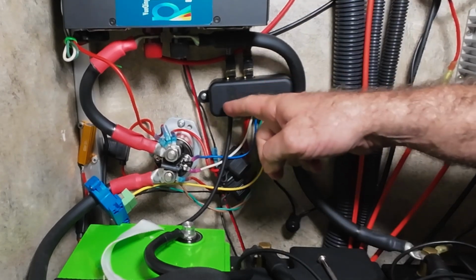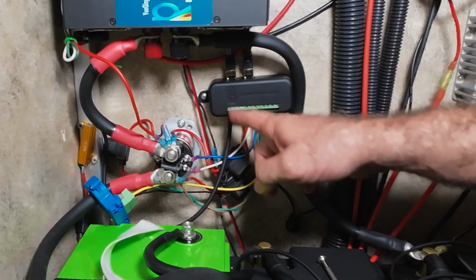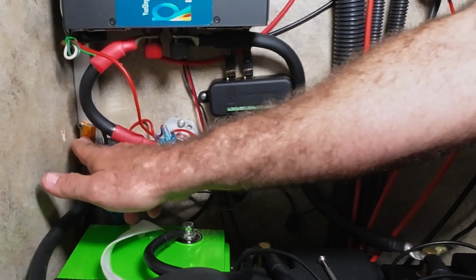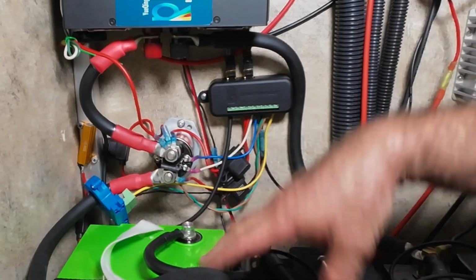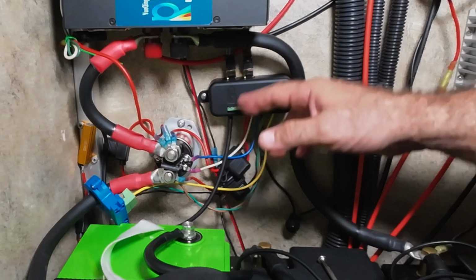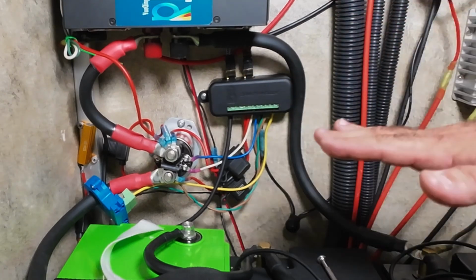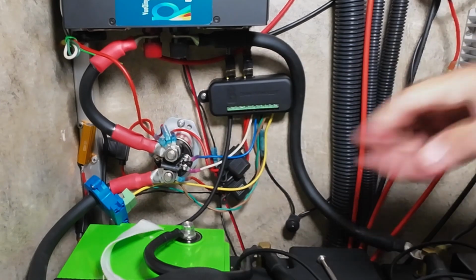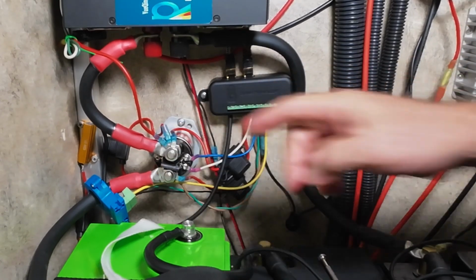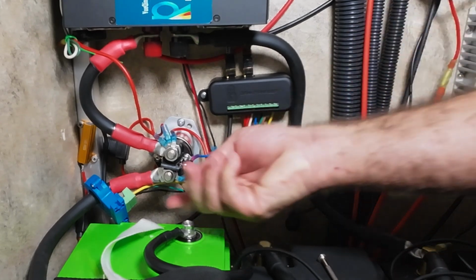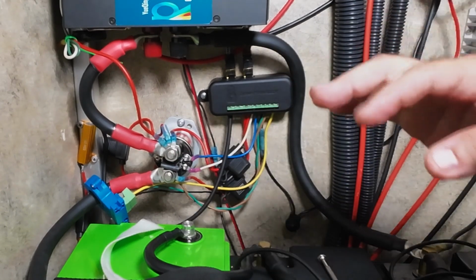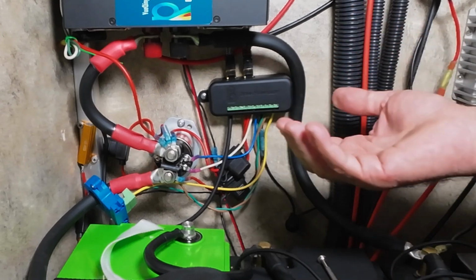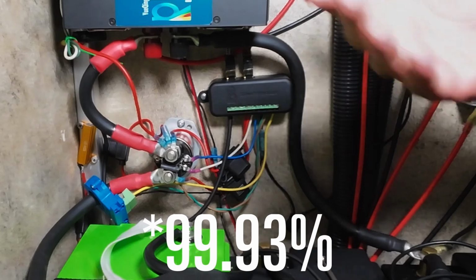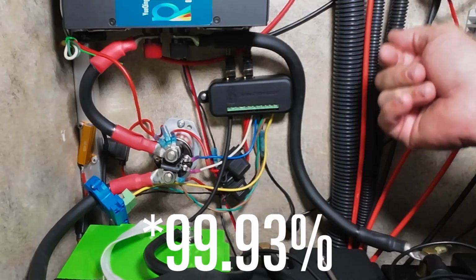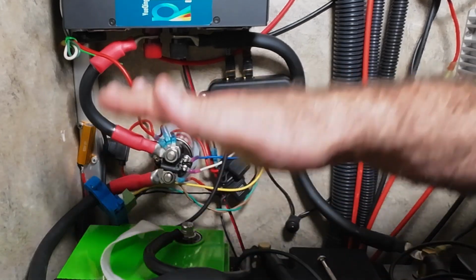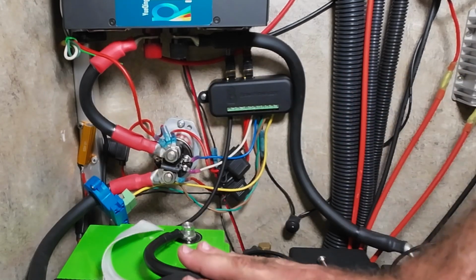So what will happen is the BankManager will make ground contact with this pin, and that will cause this resistor to come on and make heat out of the batteries. So the batteries will discharge, and they'll keep discharging until the BankManager sees their voltage has dropped down to a safe level. At that point, it shuts this off, and I found pretty consistently in my tests that when it shuts off, the display that tells you the percent of charge will say that you have remaining 99.97% of your capacity.